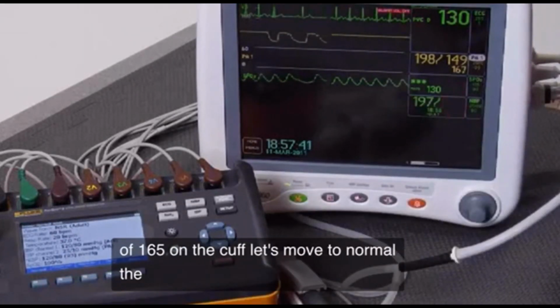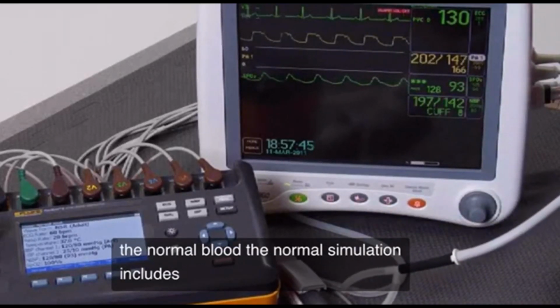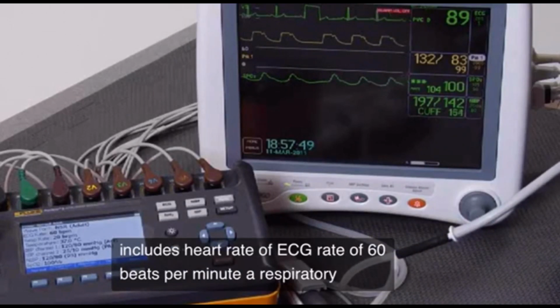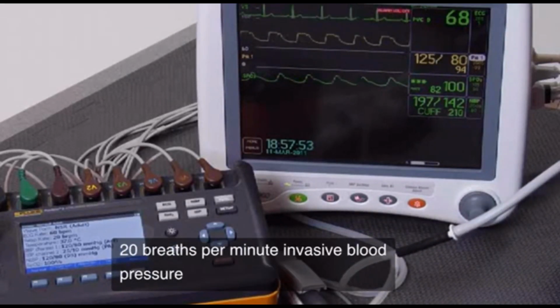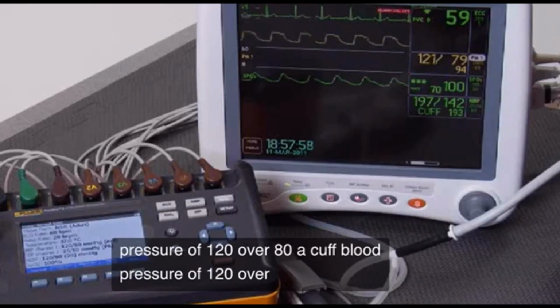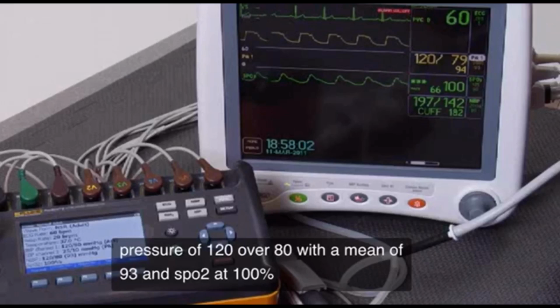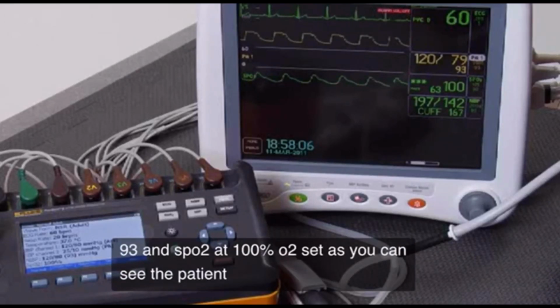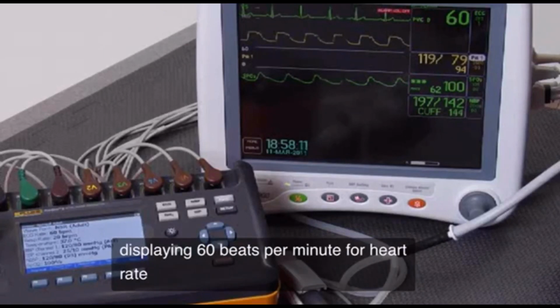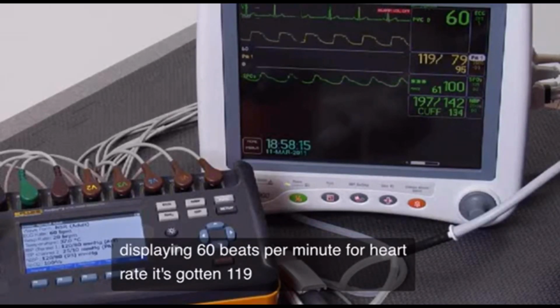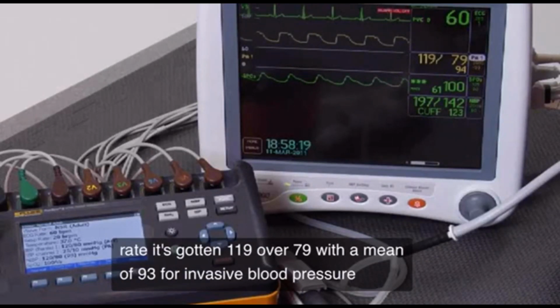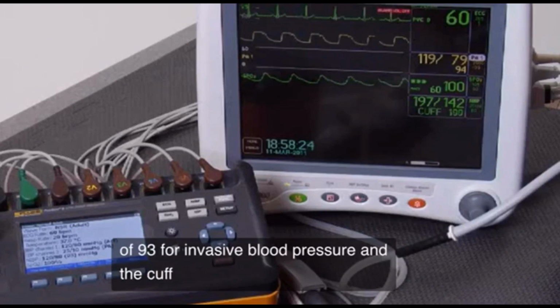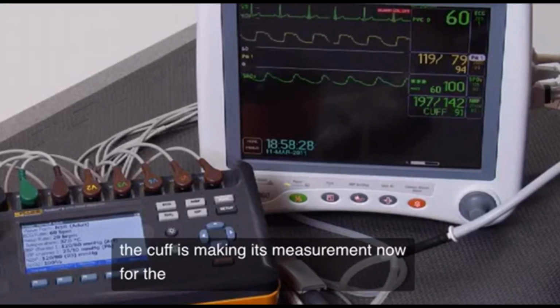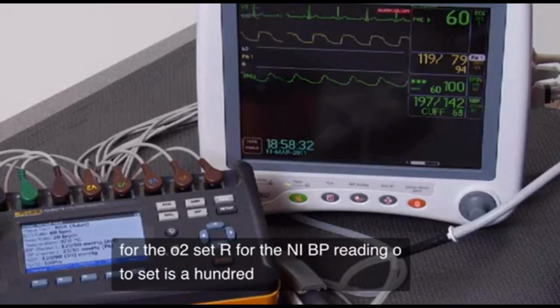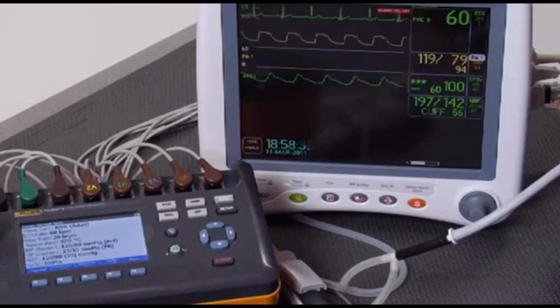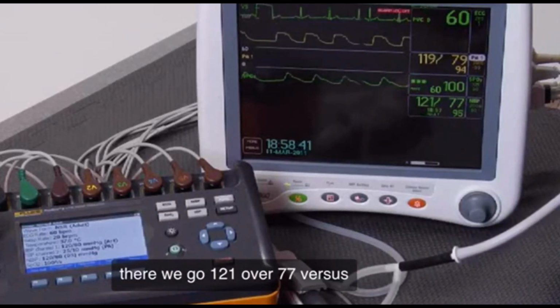Let's move to normal. The normal simulation includes an ECG rate of 60 beats per minute, a respiratory rate of 20 breaths per minute, invasive blood pressure of 120 over 80, and a cuff blood pressure of 120 over 80 with a mean of 93, and SpO2 at 100% O2 sat. As you can see, the patient monitor is already displaying 60 beats per minute for heart rate. It's gotten 119 over 79 with a mean of 93 for invasive blood pressure. And the cuff is making its measurement now for the NIBP reading. O2 sat is 100%. There we go, 121 over 77 versus 120 over 80, pretty good.